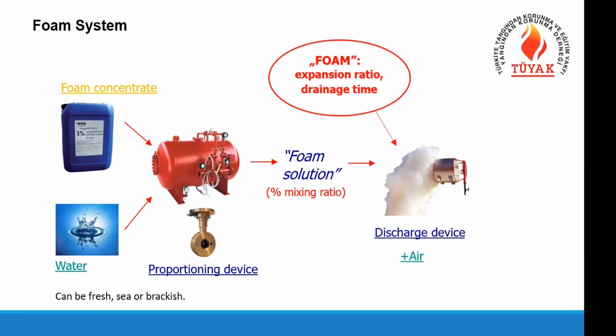And we have two important pieces of information that make the foam suitable for fire protection: expansion ratio and drainage time. These are technical details that we normally cover in our technical trainings, but it's important to know that this is not a normal soap, not like standard bubbles. These are tested in fire situations, in different fire scenarios and different applications, and they have a very special expansion ratio and drainage time that we call the stability of the foam. So you cannot use any soap for foam systems.